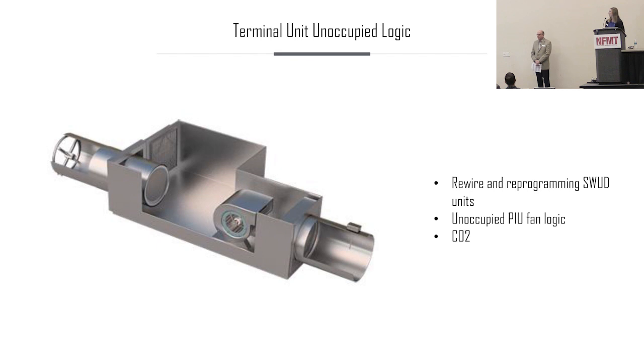So lastly, CO2. Implement demand control ventilation. You can install some CO2 meters and then ramp down those flow rates. If the space is unoccupied, then you don't need to ventilate the space. So all of this just goes back to trying to reduce that air handler energy, because that's where your savings are going to be.